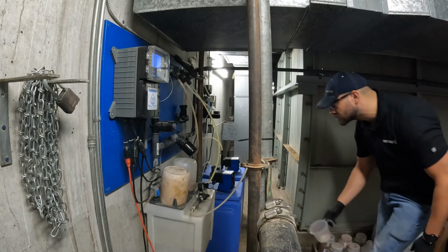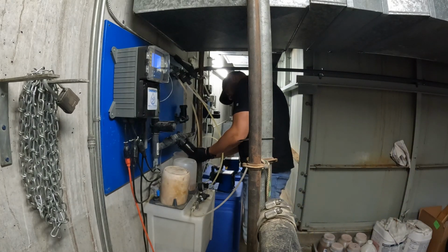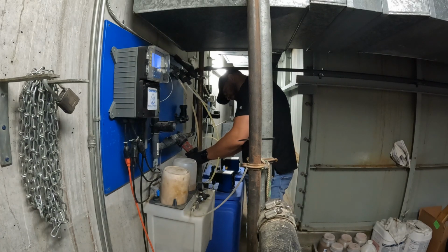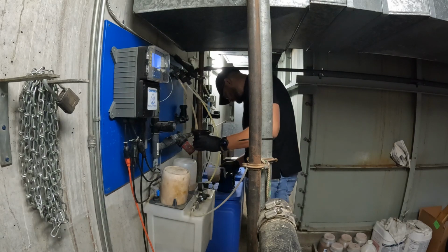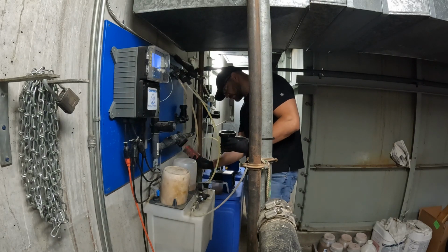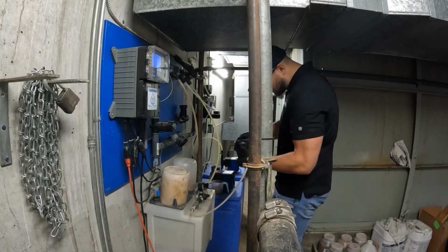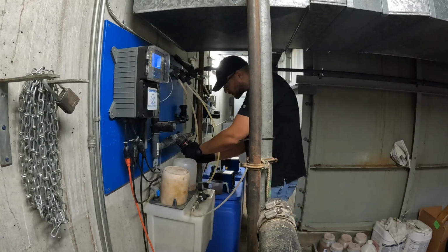Next, we will clean out the strainer basket. Note that not all manifolds will have a strainer. Be sure to use a cup or bucket to catch any water that may spill out when removing the strainer. Clean out the strainer cup and basket and then replace it back onto the manifold. Always remember to avoid over-tightening any sensors and connections on the manifold to avoid any cracks.